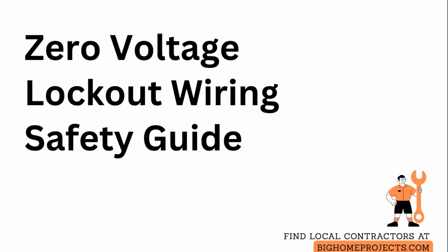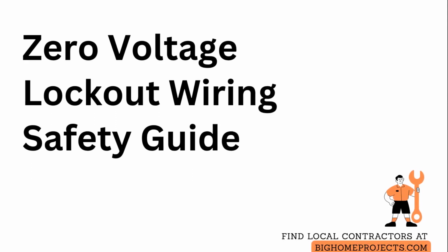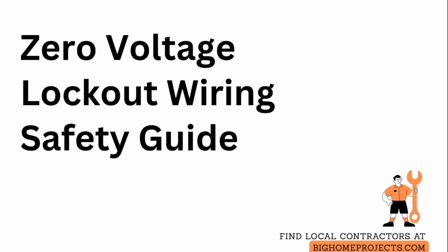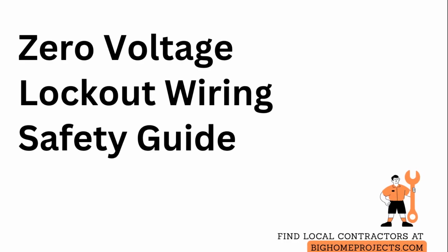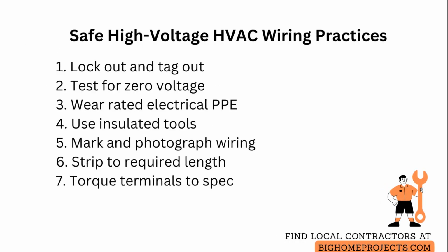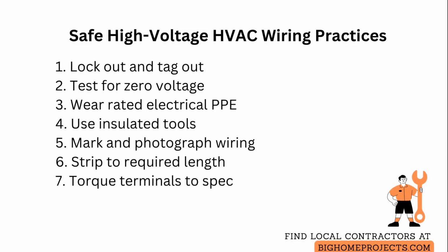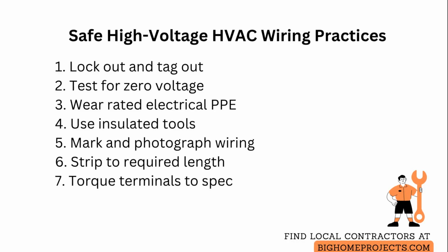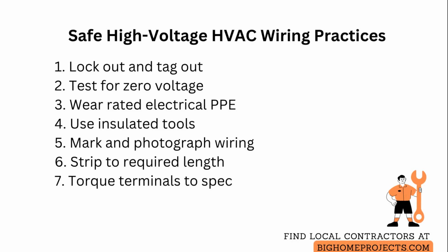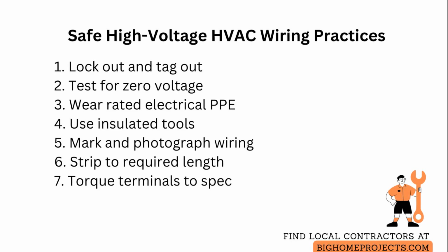Always cut power and verify zero voltage before touching any high voltage HVAC wiring to prevent shock or equipment damage. When preparing to disconnect or reconnect high voltage wires on HVAC components, first lock out and tag out the circuit at the breaker and at any fused disconnects. Then test the wires with a reliable voltage tester to confirm there is no live voltage present.